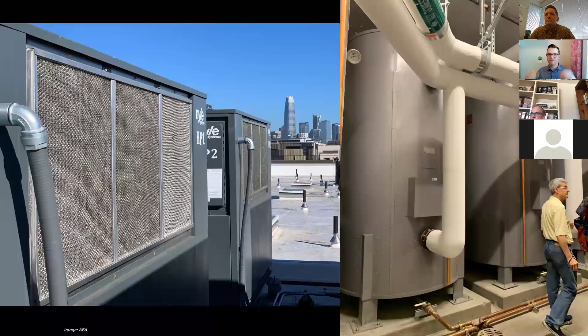Let's see another example. Here we have larger heat pumps for a bigger building. This is actually on the roof of a large all-electric dorm at UCSF in Mission Bay in San Francisco, a brand new all-electric dorm. They have something like 190 beds for student housing, so they get very high hot water demand. So heat pumps on the roof, and in this case they decided to put the storage tanks on the ground floor, so you can separate them. They don't have to be right next to each other. Generally it's good to have them pretty close, but you can separate them if you need to. That's an example on a new all-electric building in San Francisco.